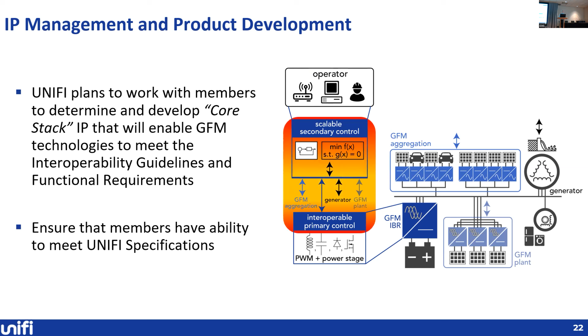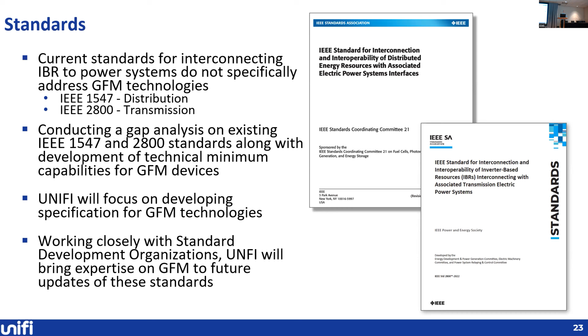On the standards front, one of the things we're most recently doing is working with standards development organizations to see how grid forming fits into the existing standard fleet. Things like IEEE 1547, which is interconnection rules at the distribution level, and the newly published IEEE 2800, which is inverter-based resources at the transmission level. Neither of those really completely adequately cover grid forming inverters today. But we'd like to take our lessons learned and plug those into the standards as they get revised. 1547 already started its revision for the next round, so we have a way of mapping into the existing standards, and hopefully we can take advantage of that instead of writing a whole new standard on grid forming technologies.